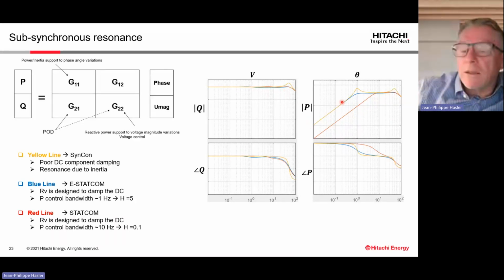And you see that the blue curve is the response of the E-STATCOM, and the red one is the response of a pure STATCOM. That means a STATCOM without energy storage. And the difference is the breaking frequency. That means when our power control starts to be activated. When we have an E-STATCOM, we start to activate the power control when the frequency is below 1 Hertz. For the STATCOM, we are a bit higher, maybe at 20 Hertz.